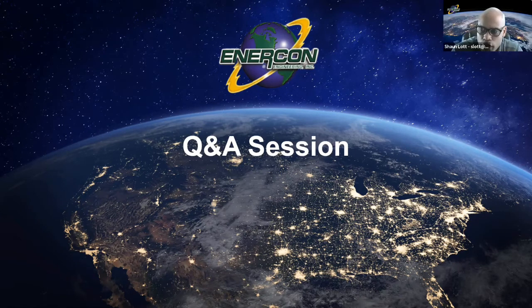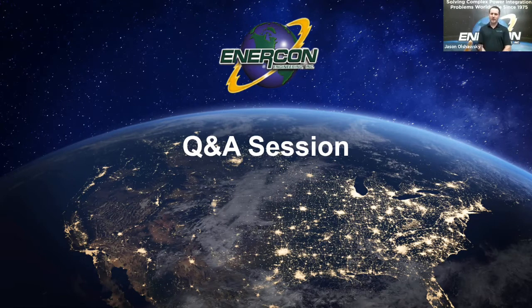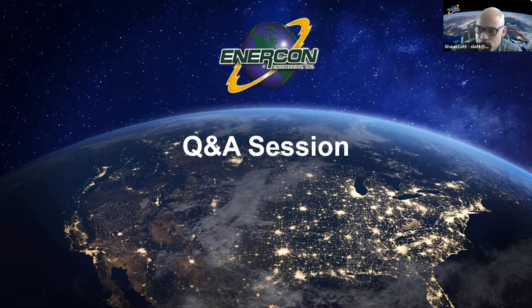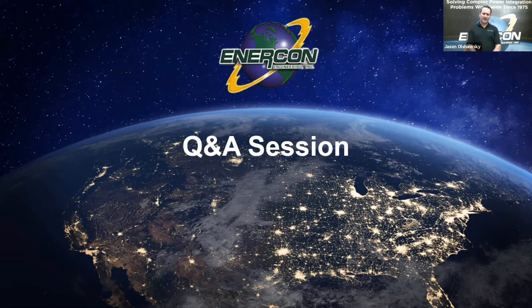Okay, all right. I'm reading a question here coming off of Zoom. Does the NEC classify transfer switches as switchgear? That's part 1 of the question. And part 2 is, are transfer switches manufactured to the same UL ratings as other switchgear? That's a good question. Actually, the UL ratings are going to be different on transfer switches in some aspects. What was the first part of that question again, Sean? The first part is, does the NEC classify transfer switches as switchgear? I don't believe so. I would definitely have to go back and look that one up again in the NEC, but I believe there's a different article for transfer switches, more so than switchgear.